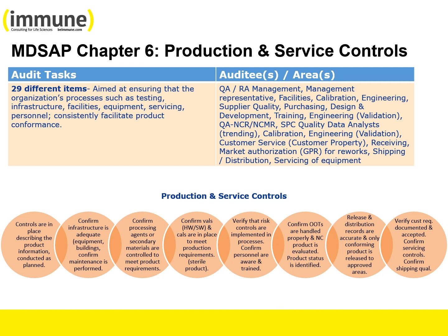achieve the planned results. Next, the company is expected to ensure that there are implemented procedures for validation of the application of any computer software for production and service processes that affect the ability of the product to conform to the specified requirements, including validation of computer software used in the quality management system, and the company has maintained records for each batch of medical devices that provides information for traceability and confirmation that the batches have met the specified requirements. The company is responsible to ensure that they have documented evidence of implemented controls to protect customer property, including intellectual property, confidential health information, and other forms of customer property that are used or incorporated into the products.